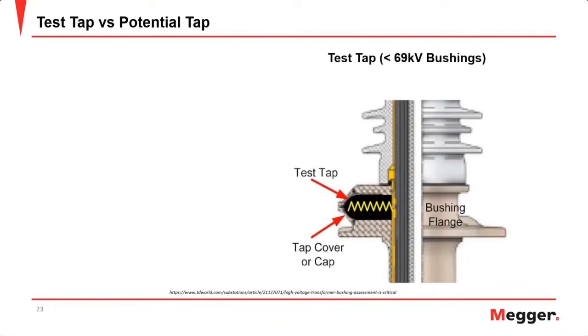The reason why it is called a test tap is because it is connected to the last foil in that capacitively graded bushing. And when that is the case, when you perform a C2 capacitance measurement, it's going to be an uncontrolled measurement. And what I mean by uncontrolled is that you are measuring from that last layer to the ground flange or the tank of the transformer.